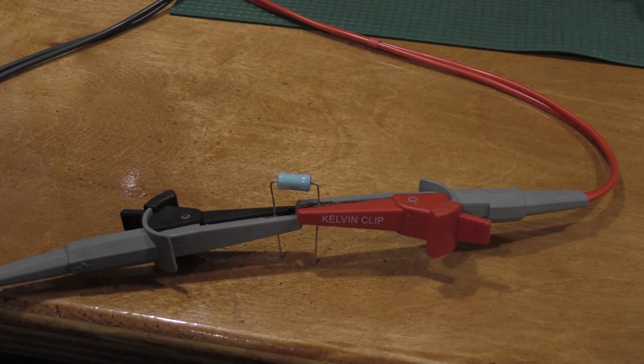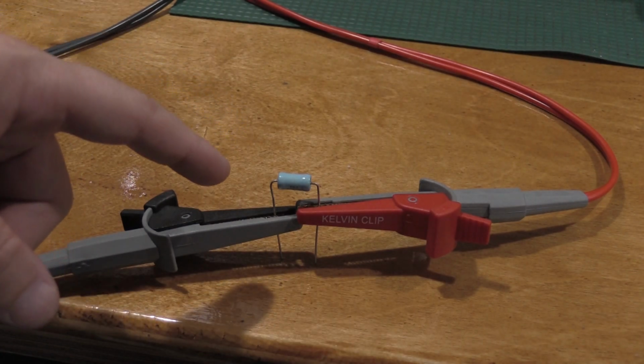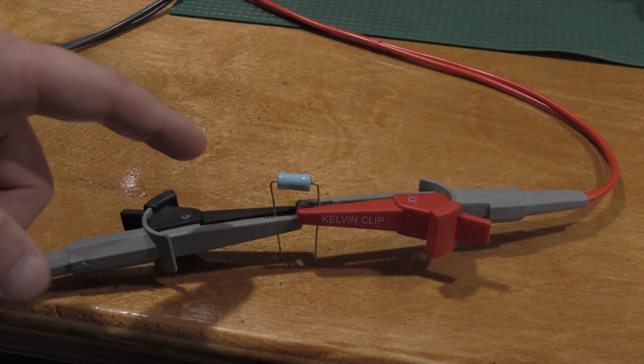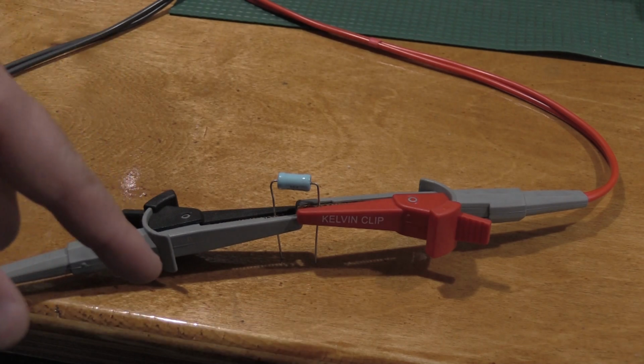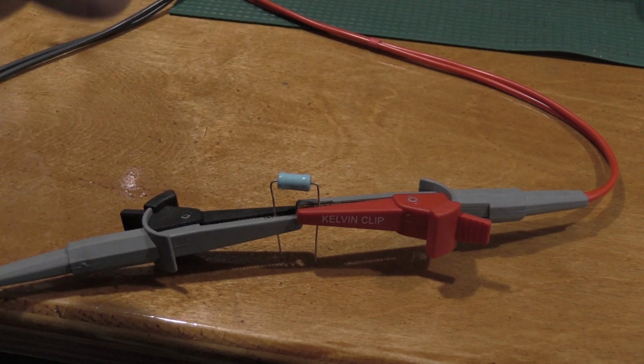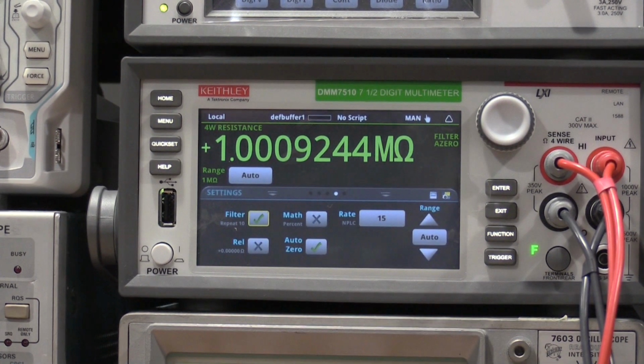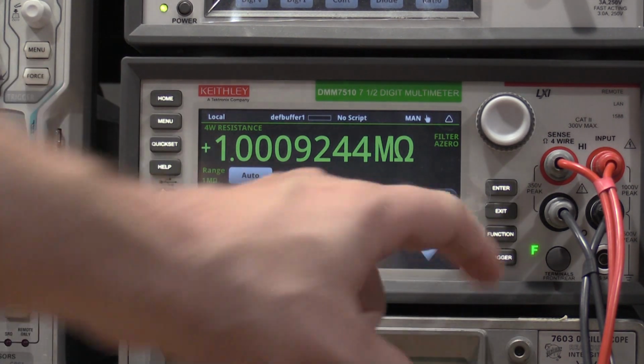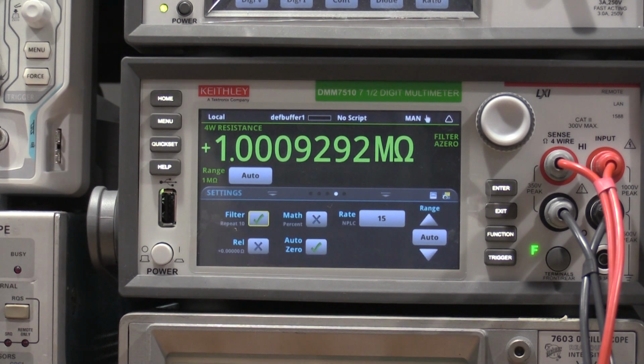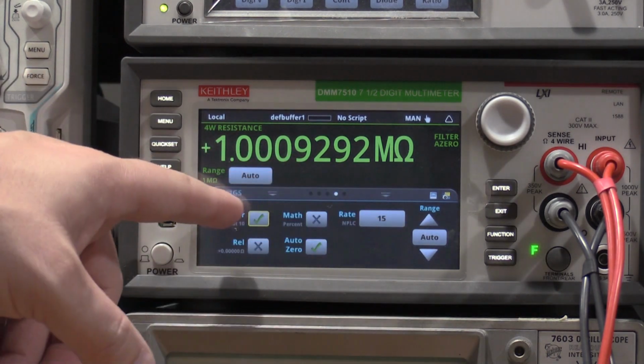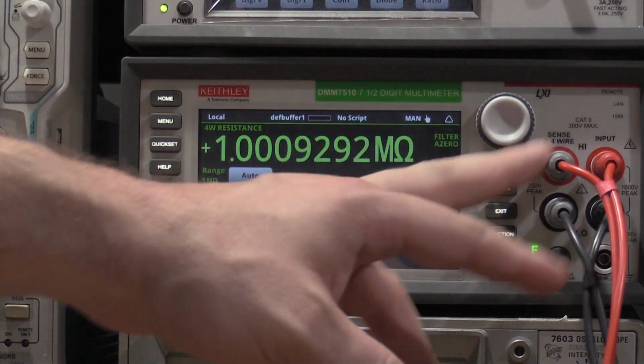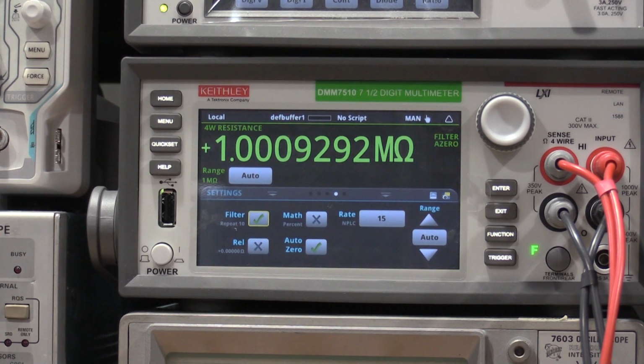So the equipment we're going to be using for this calibration is, I'm going to be using this resistor, which is a 1 mega ohm 1% resistor. The calibration wants a 0.1% resistor. This particular example measures at 0.092%. So this is within spec for the calibration. The meter's taking a while to do the measurement because I have it at its highest accuracy of 15 power line cycles plus filtering plus 4-wire measurement for the resistance, so I can get the most accurate resistance measurement possible.